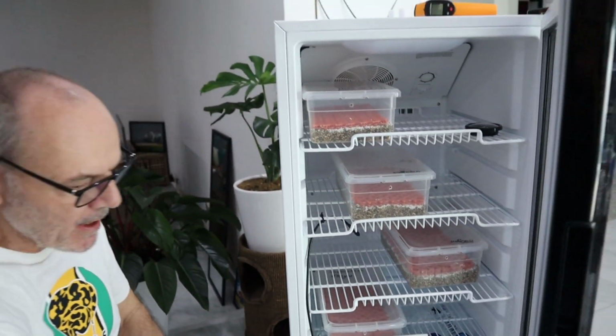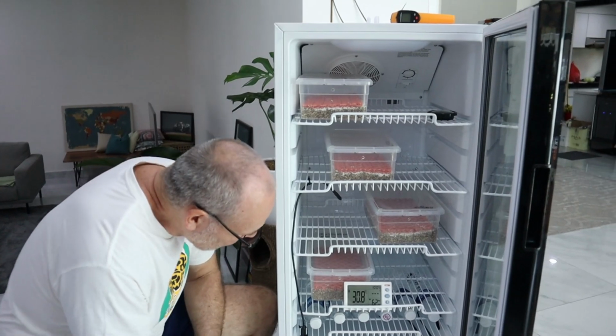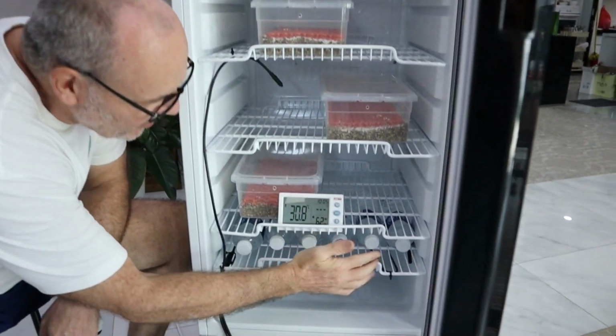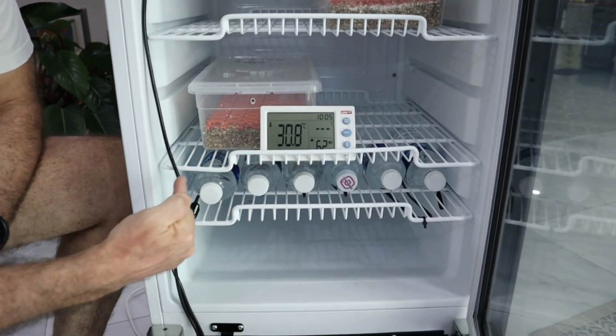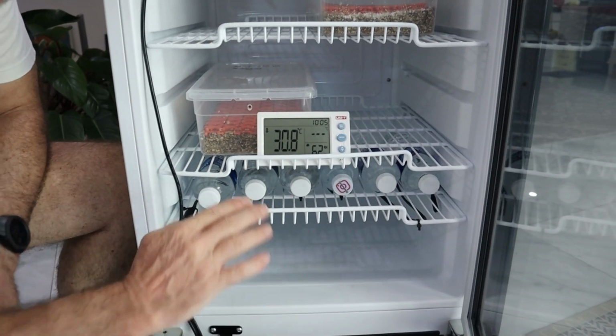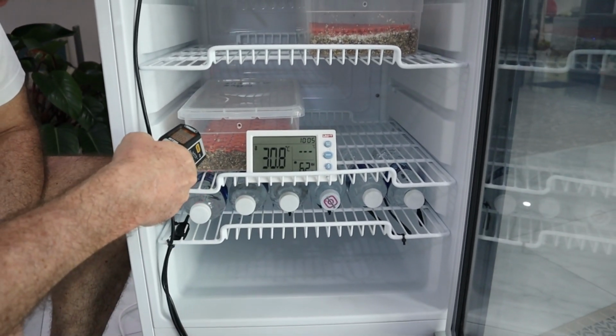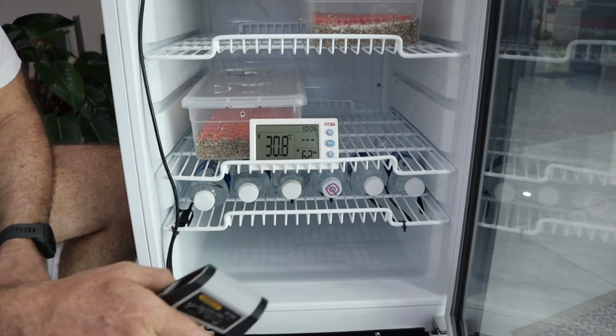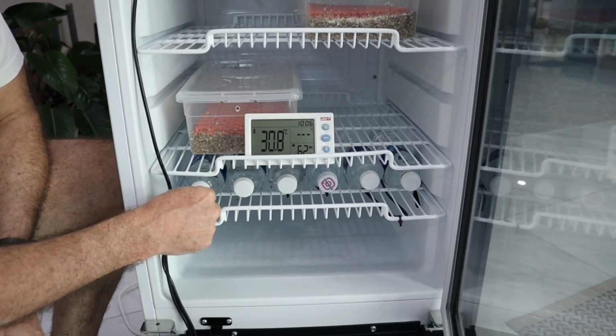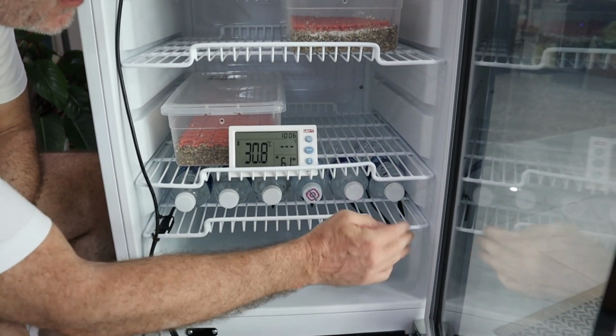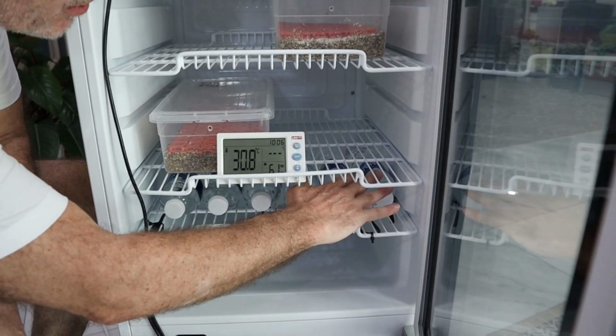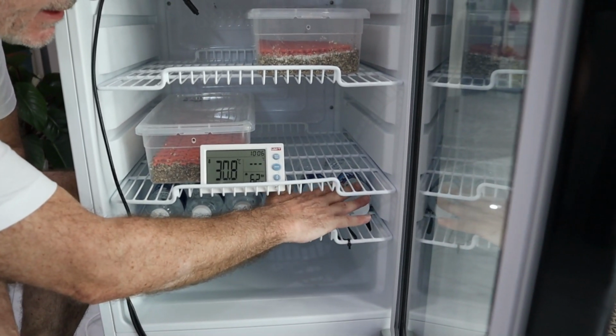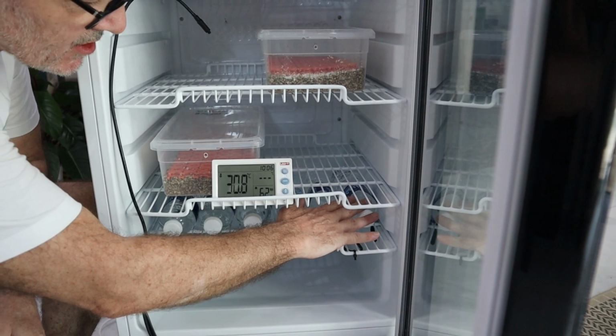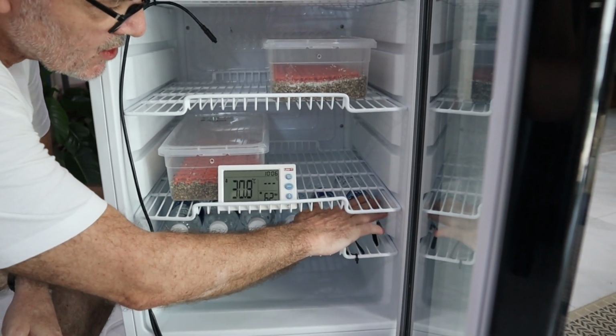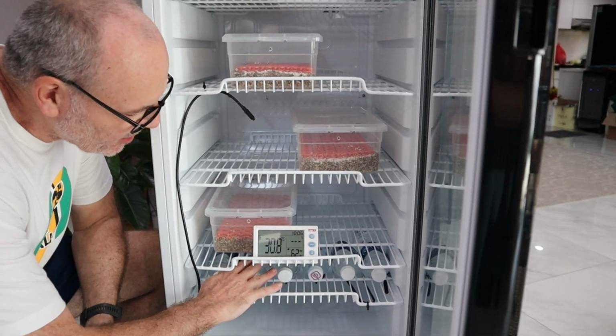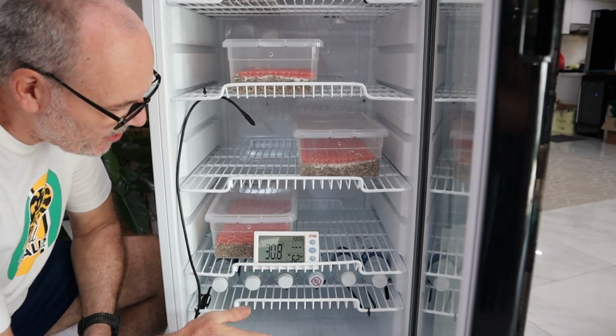What's happening here in the incubator is we've got a nice little bit of radiation heat in this local area. The water bottles have warmed up to 89.5, exactly where they should be. So we're also conducting heat into the water bottles, and these are acting as a heat sink. They're preventing temperature spikes in the incubator, and they're also nice and warm, so we very quickly get the temperature back up to what it needs to be.